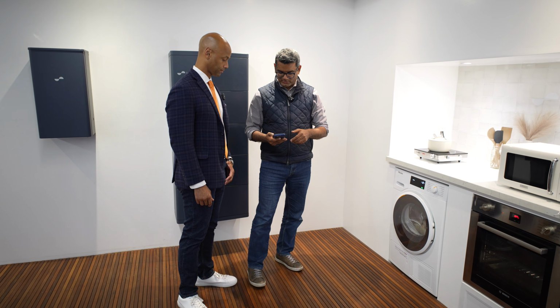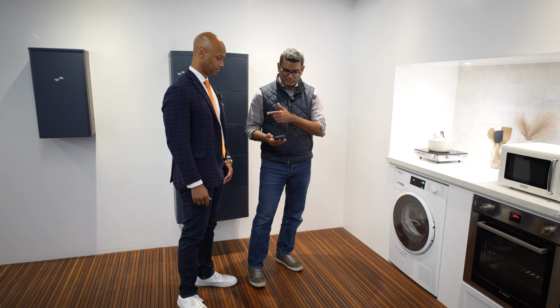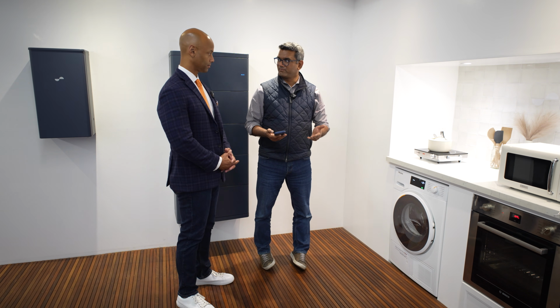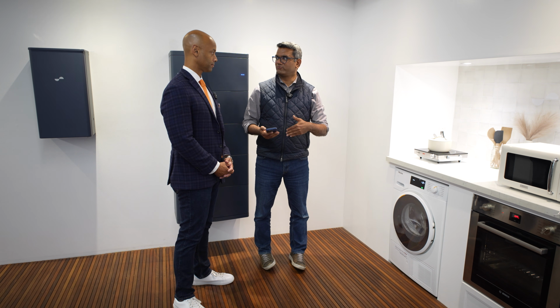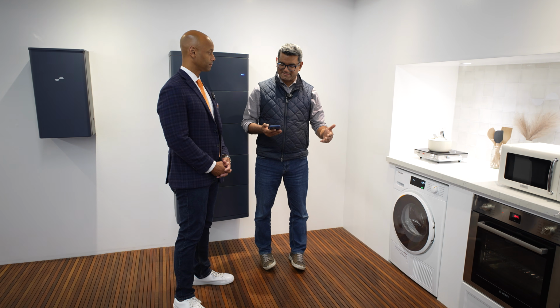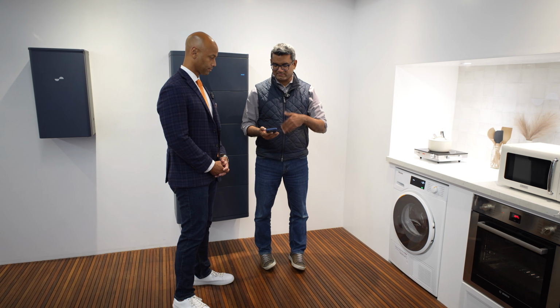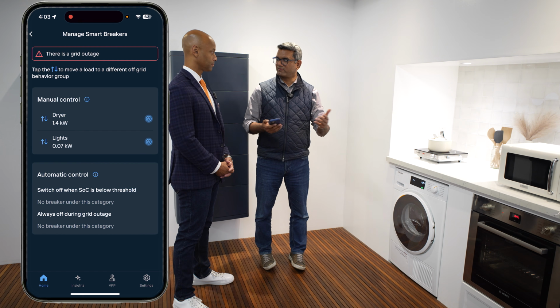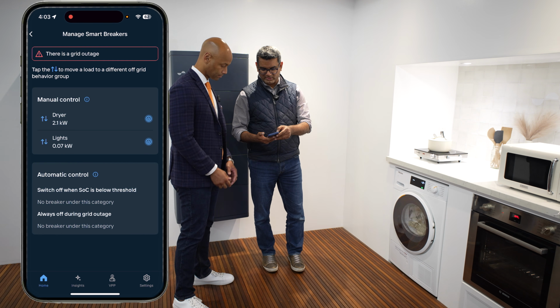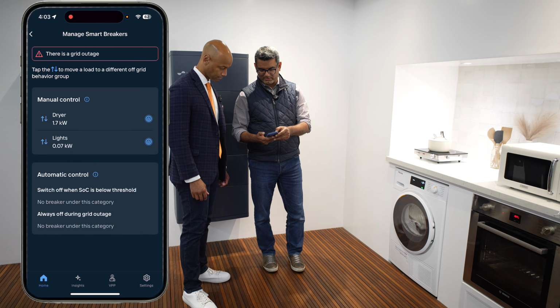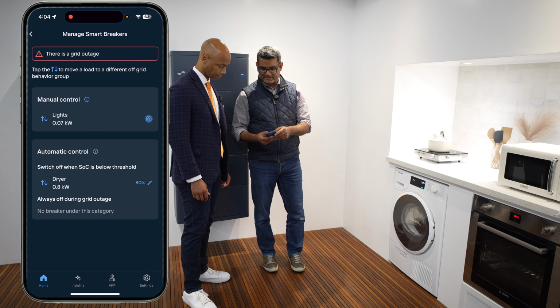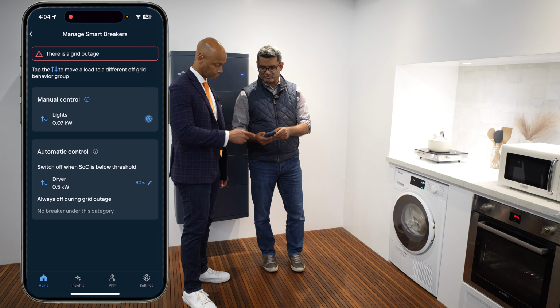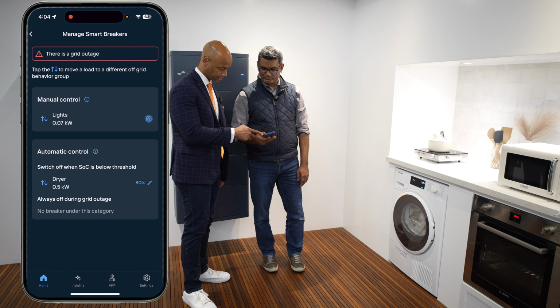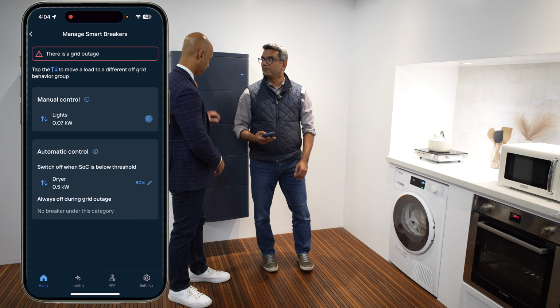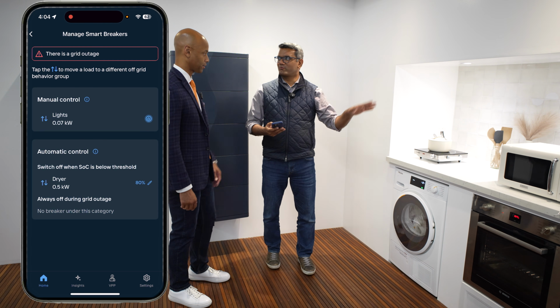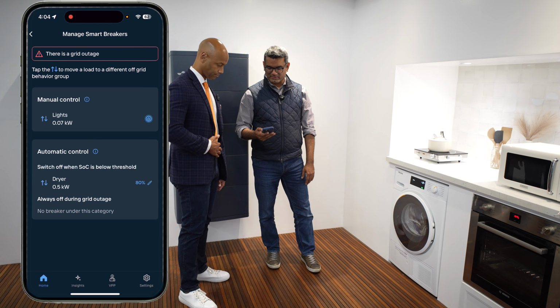The other way to manage the outage: sometimes homeowners are not at home and they want to set certain sequences of their breakers such that the system can automatically turn them off when certain situations arise. So you can say, hey, the dryer, I want it moved to automatic control, meaning it switches off when the state of charge is below a threshold. In this example, it's set at an 80% threshold, so if the battery falls below 80% during an outage, the dryer will automatically turn itself off.